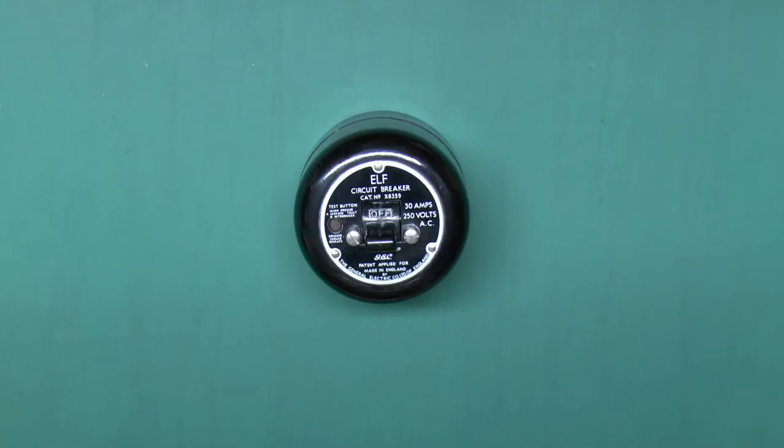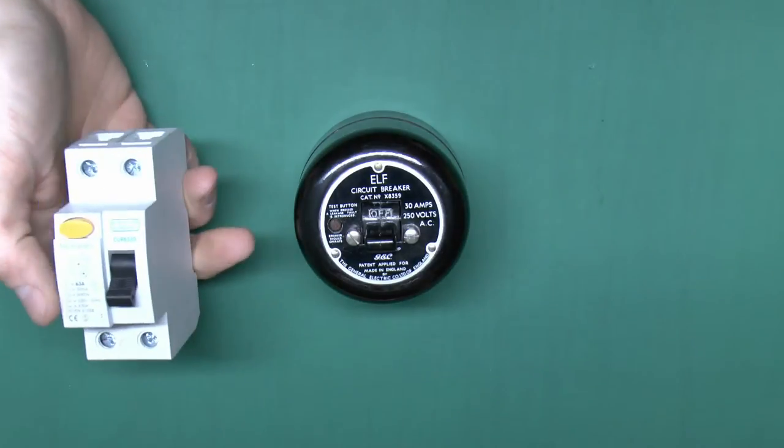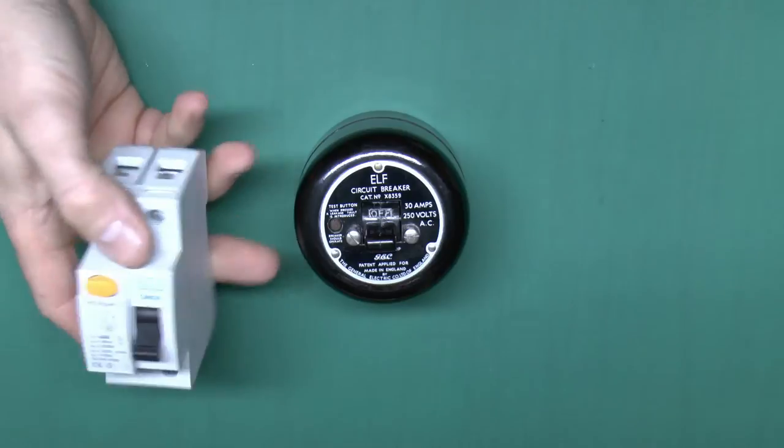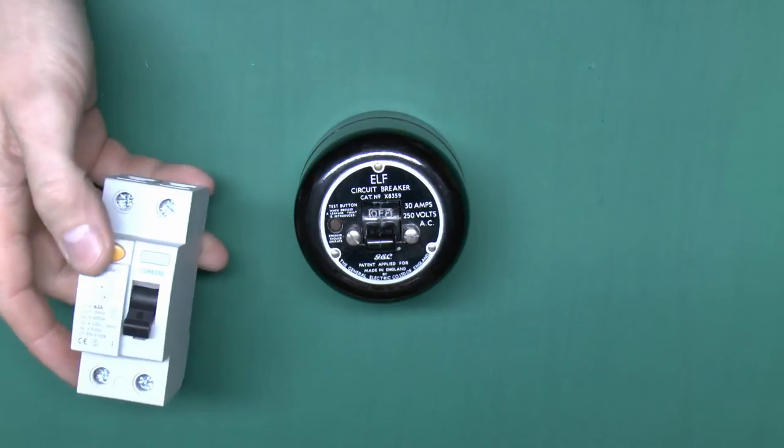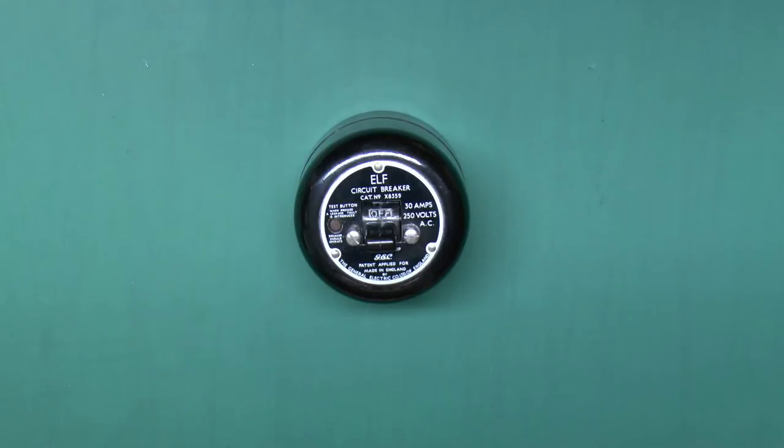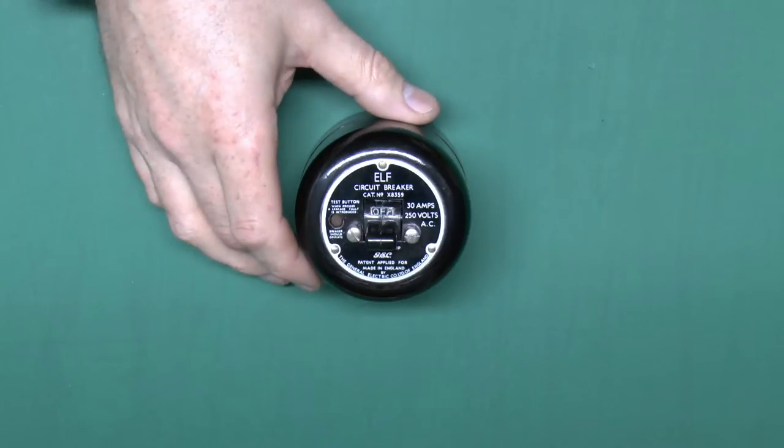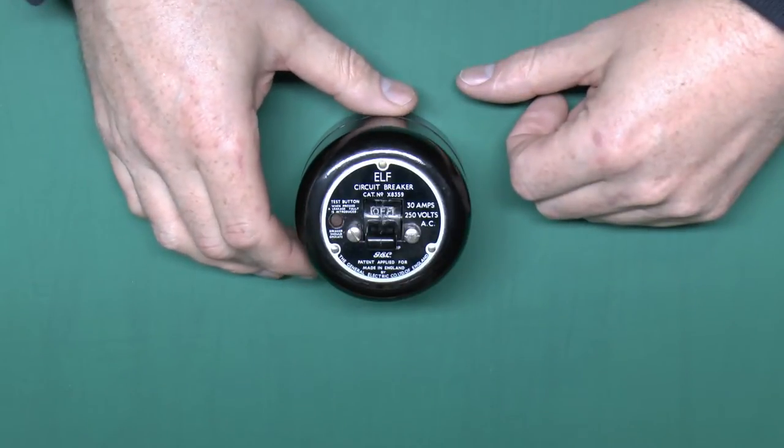Note this is totally different from the modern RCD which is a current operated device. This measures the current in and out and if there's any imbalance it will disconnect. These will protect people. These do not. That's one reason why of course they were removed from service.